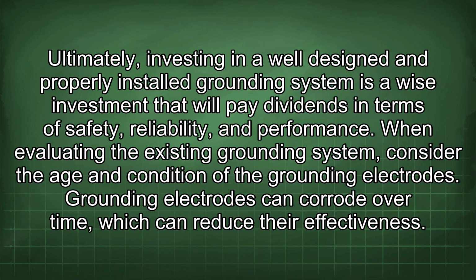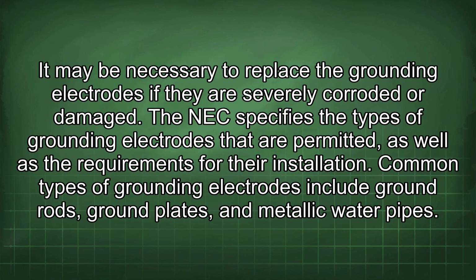When evaluating the existing grounding system, consider the age and condition of the grounding electrodes. Grounding electrodes can corrode over time, which can reduce their effectiveness. It may be necessary to replace the grounding electrodes if they are severely corroded or damaged. The NEC specifies the types of grounding electrodes that are permitted, as well as the requirements for their installation.